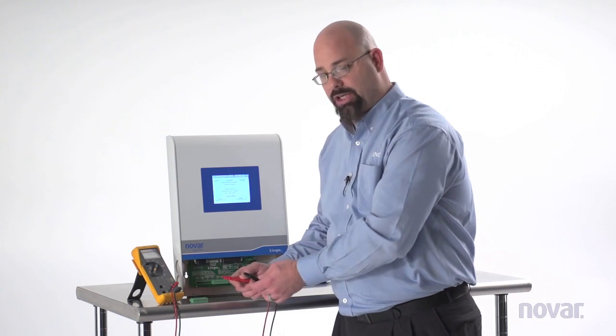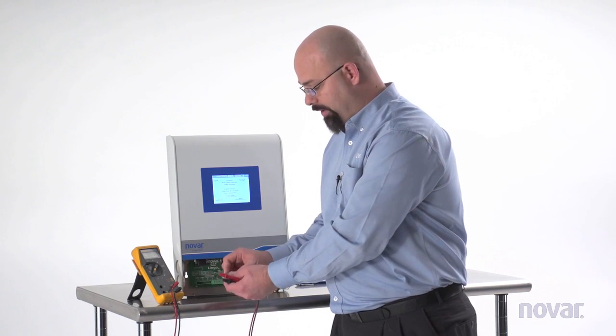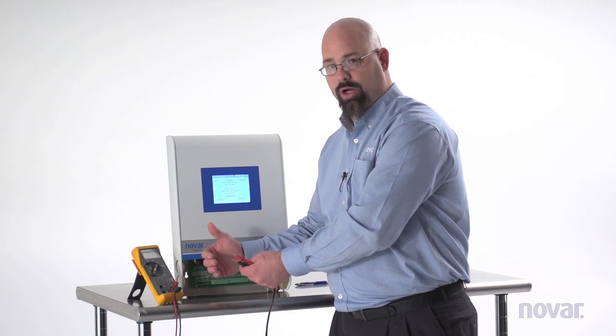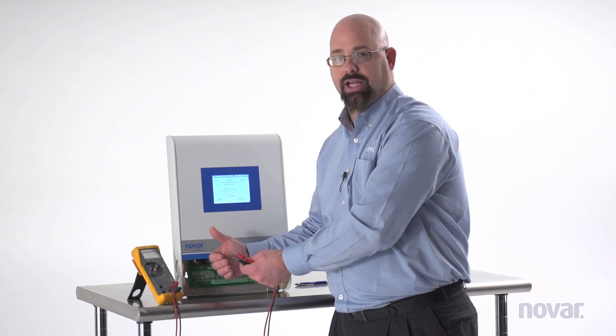I would then check the COM wires I pulled off of this the exact same way. If I have more than one set of wires on my connector, you're going to pull those wires out and check just one white to shield, one black to that shield, and then check the other wire the exact same way.